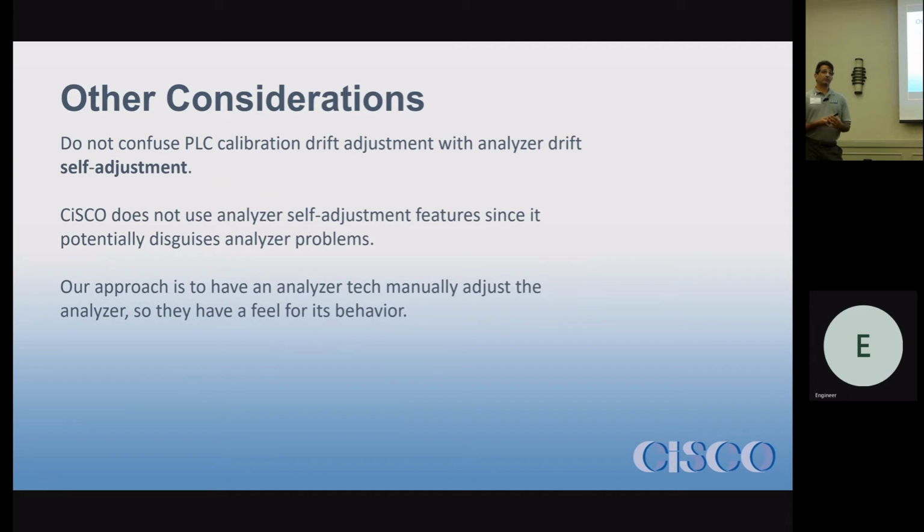So usually you have to plumb in zero and span gas directly to the analyzer, press a button on the analyzer, and it'll measure its zero and span and zero off all the error so that it's a perfectly behaving analyzer. We generally don't use that in CiSCO CEMS. We've had a few requests for that by customers.